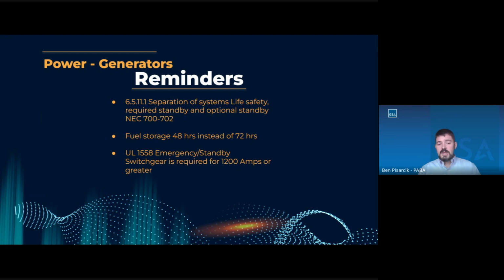Fuel storage is 48 hours instead of 72. We did not change that this time. That was last go around. I just want to bring it up as a reminder that the 2021 edition with the 2022 addendum made that change. And then the 1558 we talked about earlier with switchgear, the emergency switchgear, that's applicable to that as well. So if it exceeds 1200 amps, you're going to need to have draw out switchgear for the emergency as well.